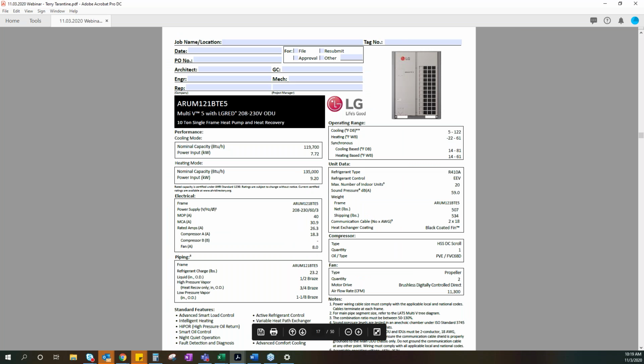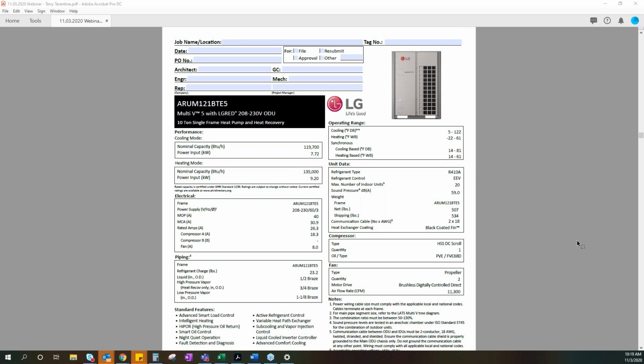Here's a submittal. Another advantage you'll see for variable refrigerant flow, and if I seem to be biased towards this, we do distribute all the systems shown. This is something that we spearheaded and we've had incredible success with. You notice that there's a very small footprint. These are modular systems, typically sized to go into an elevator. We'll just couple modules together to get the capacities we needed.